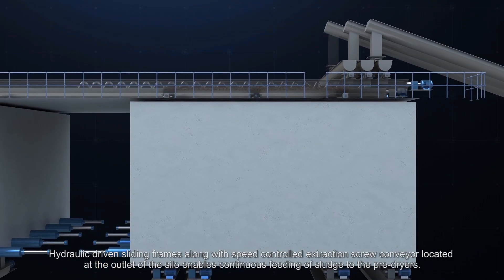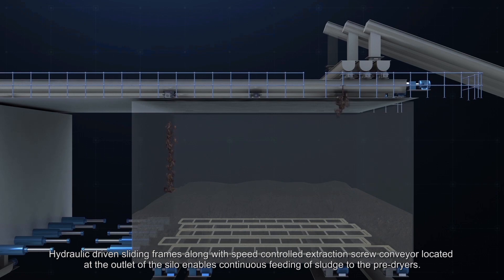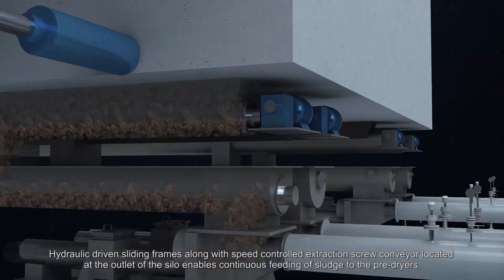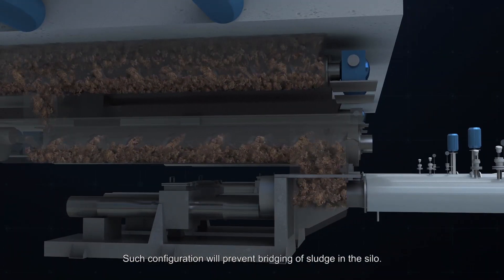Hydraulic driven sliding frames, along with speed controlled extraction screw conveyor located at the outlet of the silo, enables continuous feeding of sludge to the pre-dryers. Such configuration will prevent bridging of sludge in the silo.